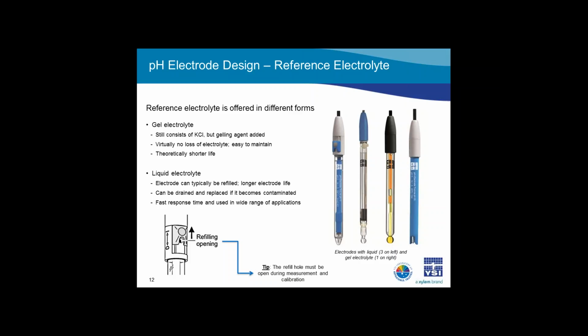If you were in the lab, I would definitely recommend an electrode with liquid electrolyte. All YSI refillable lab electrodes use 3 molar KCl for the reference electrolyte, but other manufacturers may use slightly different forms. One important tip I did want to mention is that if your electrode is refillable, it is very, very important to have the refilling opening in the open position during calibration and measurement, as you can see here.